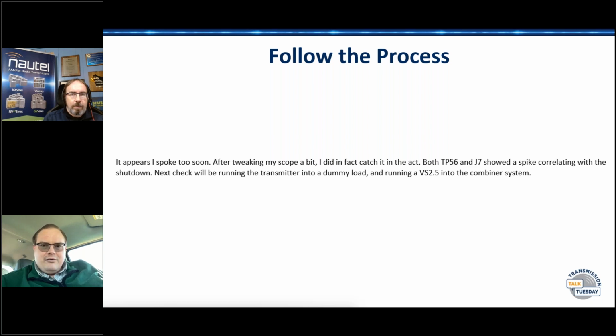So we went through and did all the troubleshooting at the transmitter. It finally got to the point where I was literally looking at what the power probe in the transmitter was seeing and what it was sending the transmitter. And sure enough, I caught in the act a very brief event that would cause the transmitter to fold back or shut down, basically to quench an arc. So the transmitter was seeing, hey, something on this line is arcing, I better quench it. And it did.